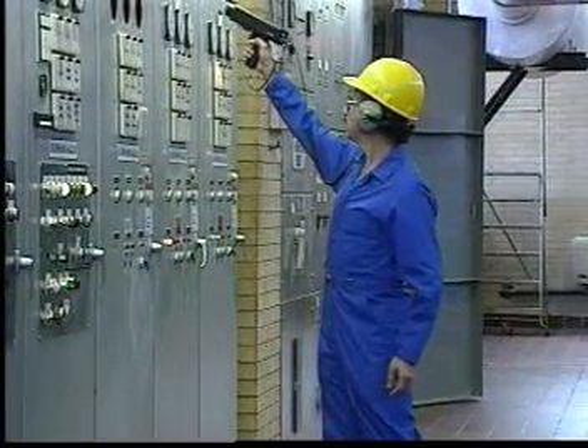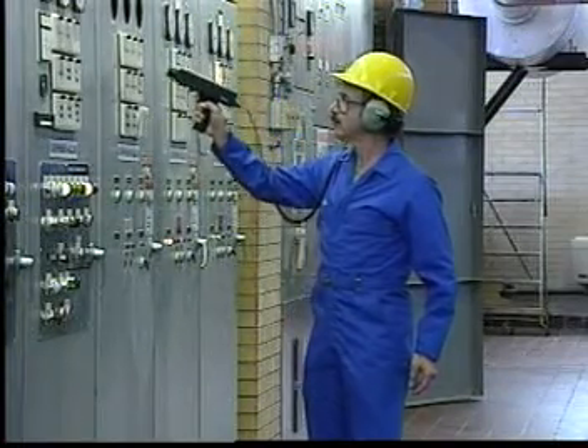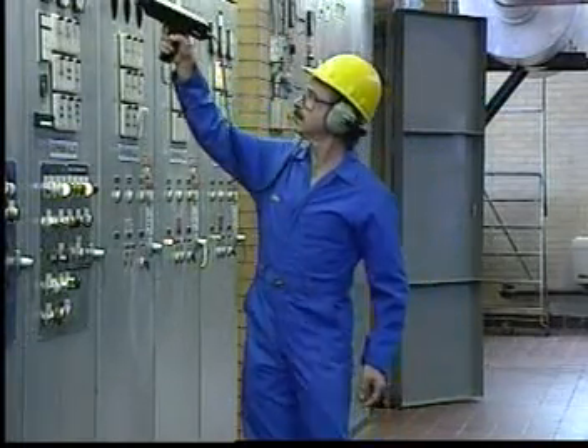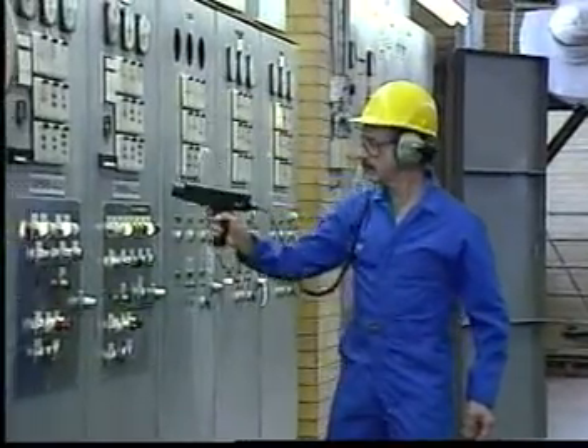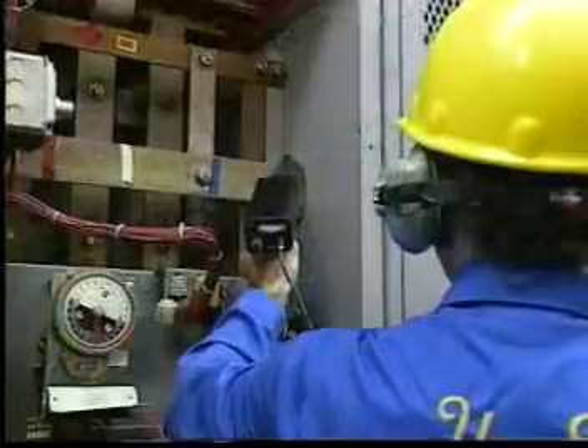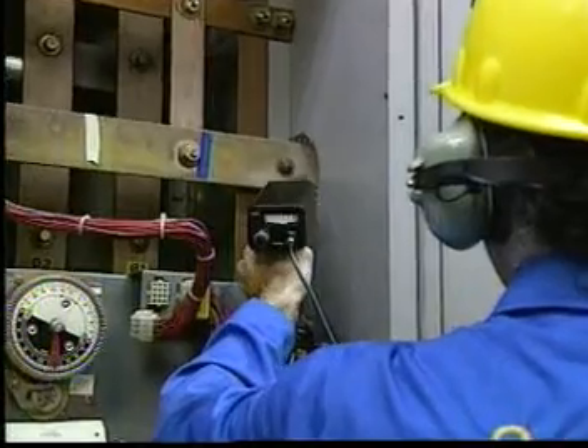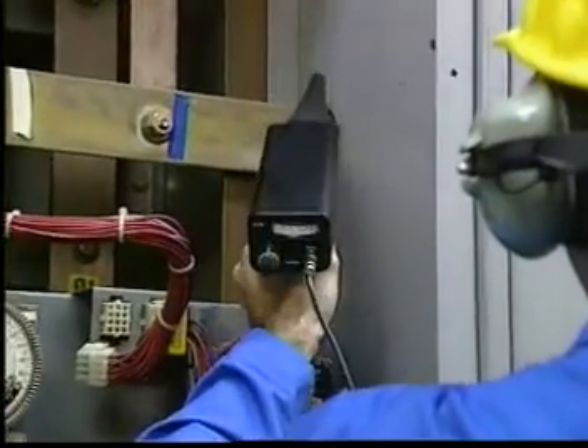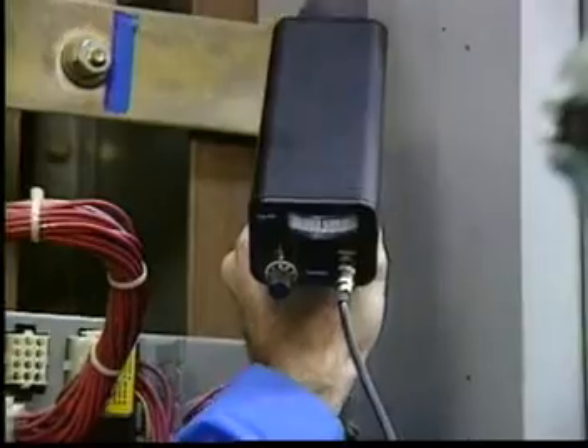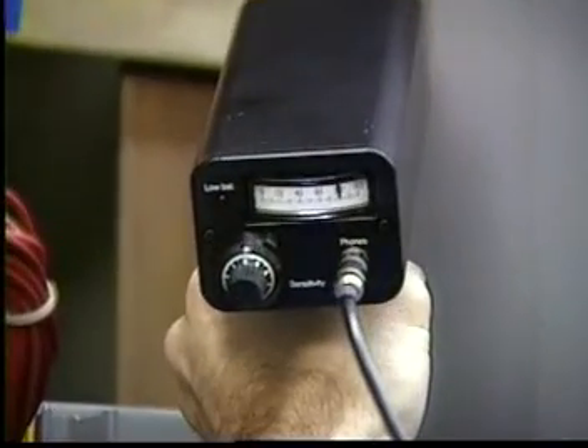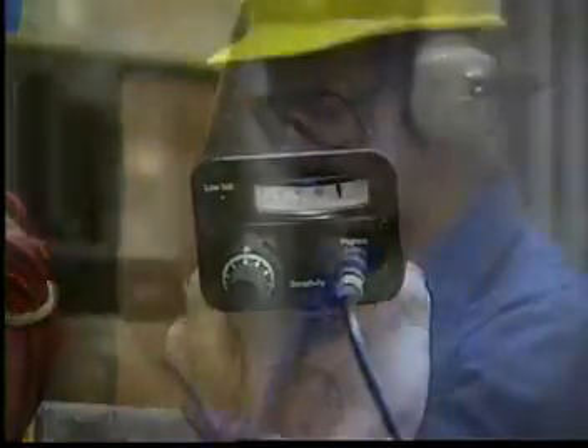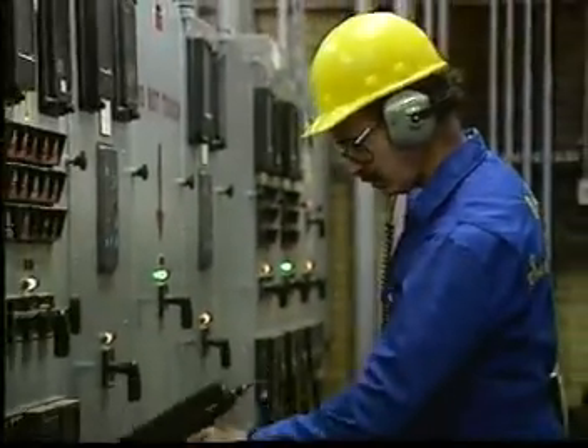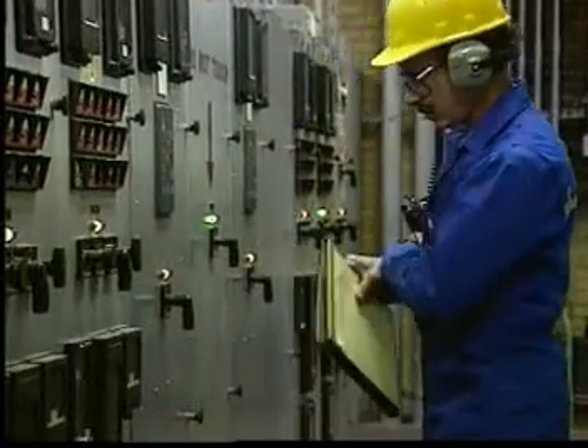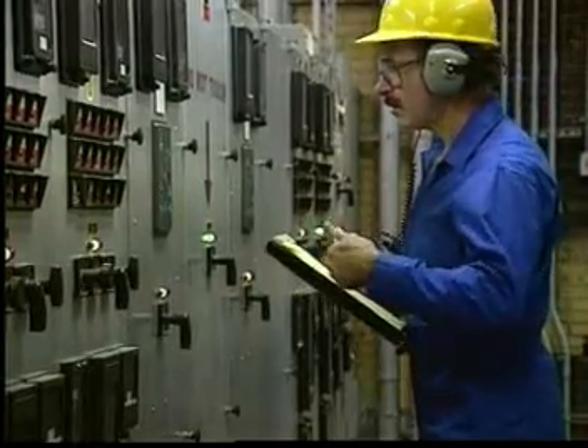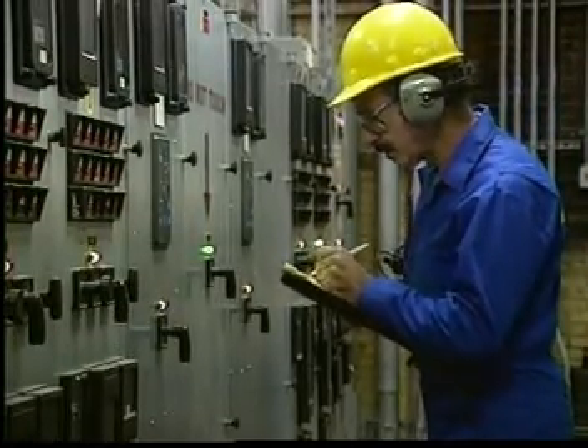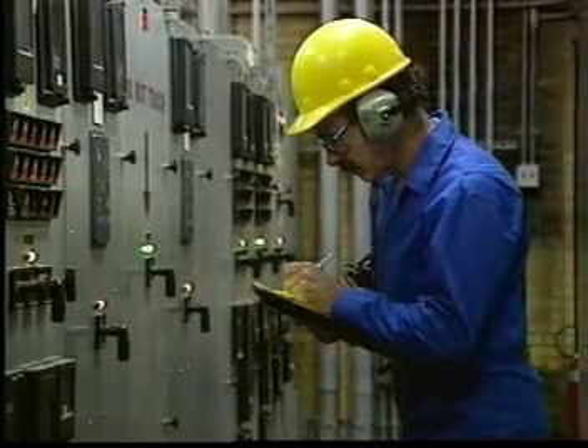In low or mid voltage environments, the sounds of electrical discharge will have less intensity. Judgments must be made based on comparisons with other normally operating equipment. The difference between a problem and normal equipment may simply be the difference between a small sound and silence. Because the difference between low, mid, and high voltage testing is one of magnitude, establishing a baseline for comparisons is essential to identify a worsening condition, especially at lower voltages where sounds may be less obvious.